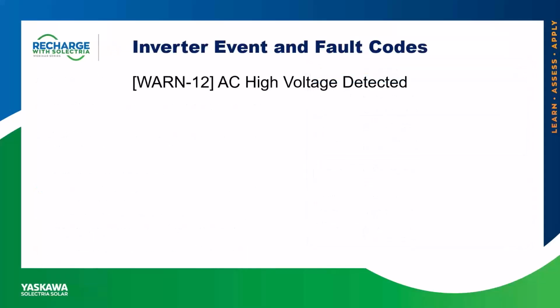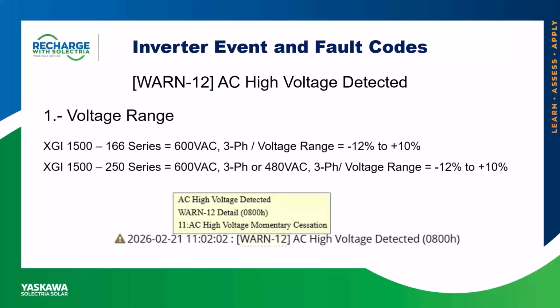The next code you may encounter on site is Warn 12, AC high voltage detected. Now, it is important to point out that depending on your inverter, the specifications are going to be different. The XGI 1500 166 series is a 600 volt AC three-phase inverter, and it has a voltage range of minus 12% to up to 10% positive. What this means is when the unit has grid connected and is producing power, the 600 volt AC inverters can go up to 660 volts AC while grid connected and producing power.